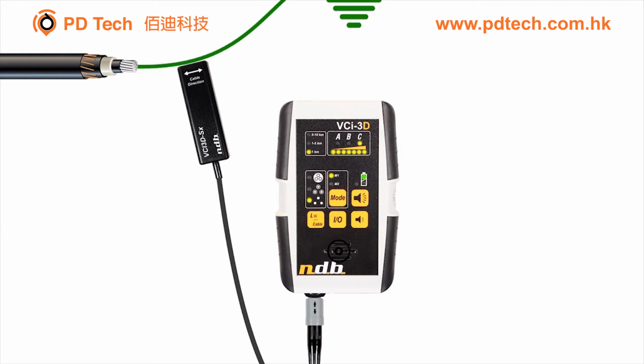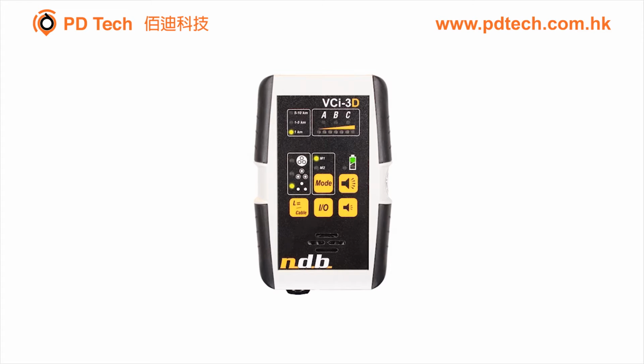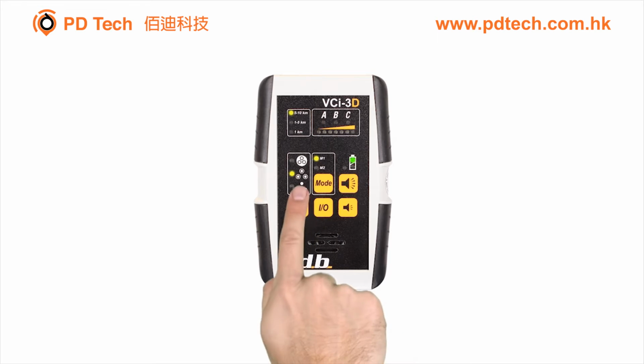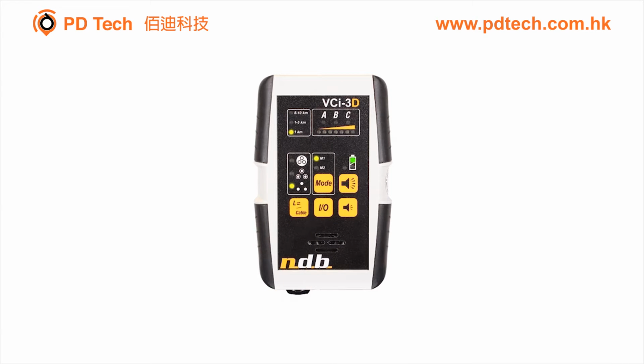The previously recorded voice message of the transmitter will be played back while applying the sensor on phase A and on phase C. Depending on the length and cable properties, the detector gain may need to be increased. Press the gain adjustment button to increase between the gain presets to obtain sufficient signal levels. It is always advised to start from the lowest gain and increase as needed.